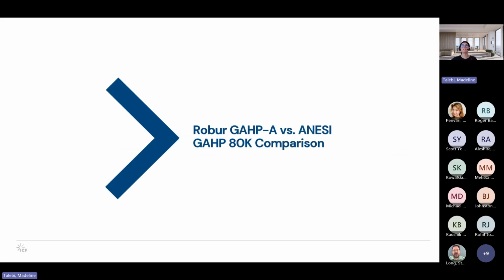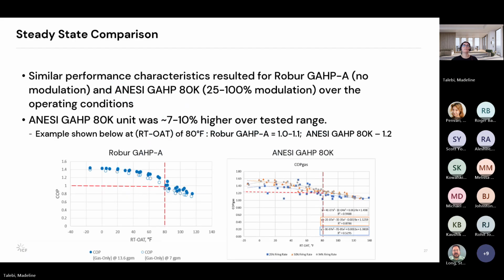And then finally, looking at the Robur GAHP-A unit versus the ANESI GAHP 80K unit. Overall, there was similar performance between the two units over the operating conditions that were tested. If we look at the ANESI GAHP 80K unit, it was about 7 to 10% higher over the tested range. It was similar, but ultimately the ANESI did show a higher COP than the Robur, and I believe it is attributed to the modulating controls that are built into the ANESI.